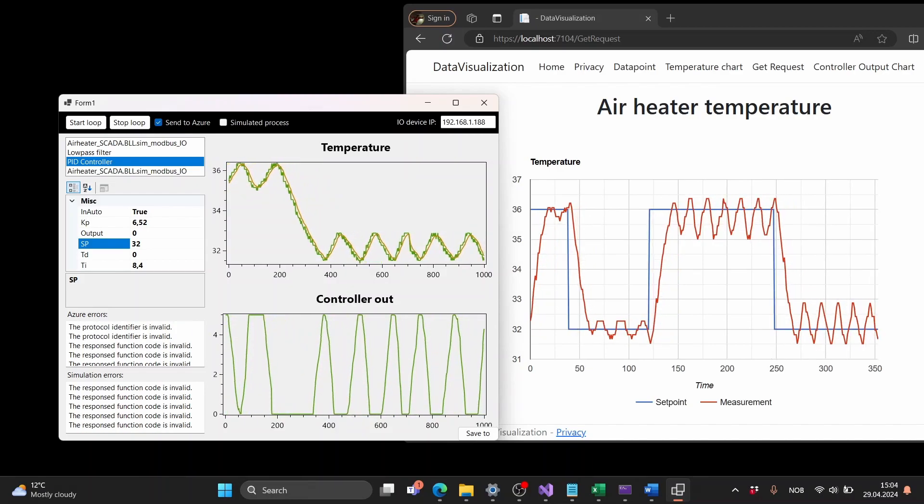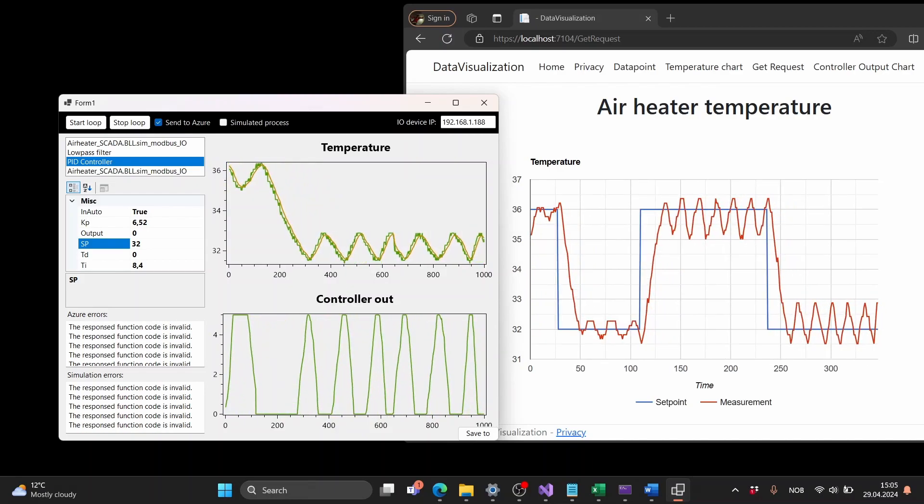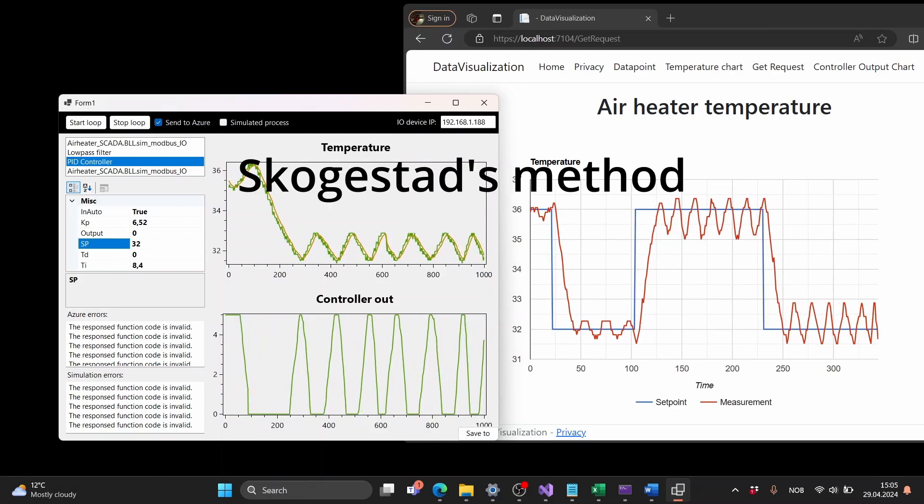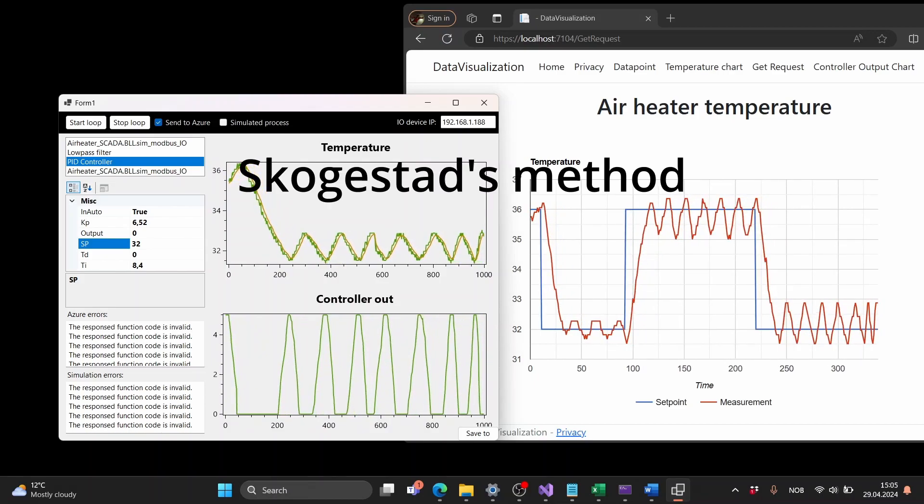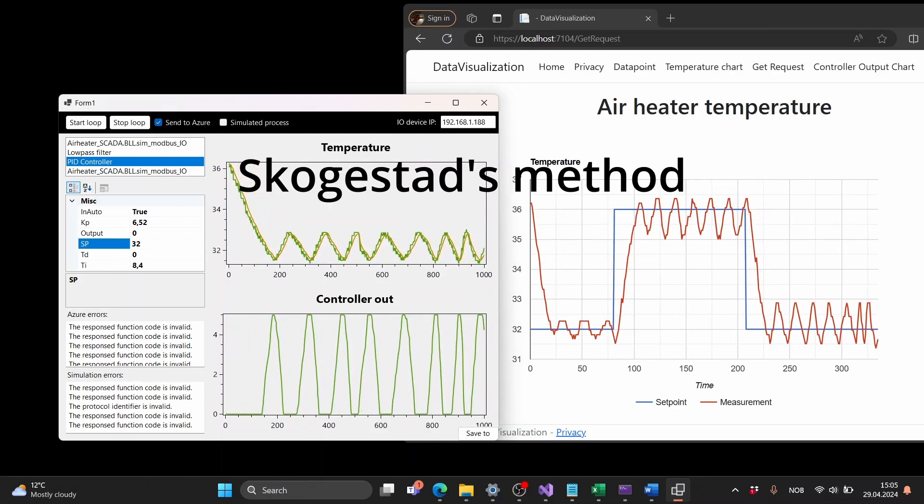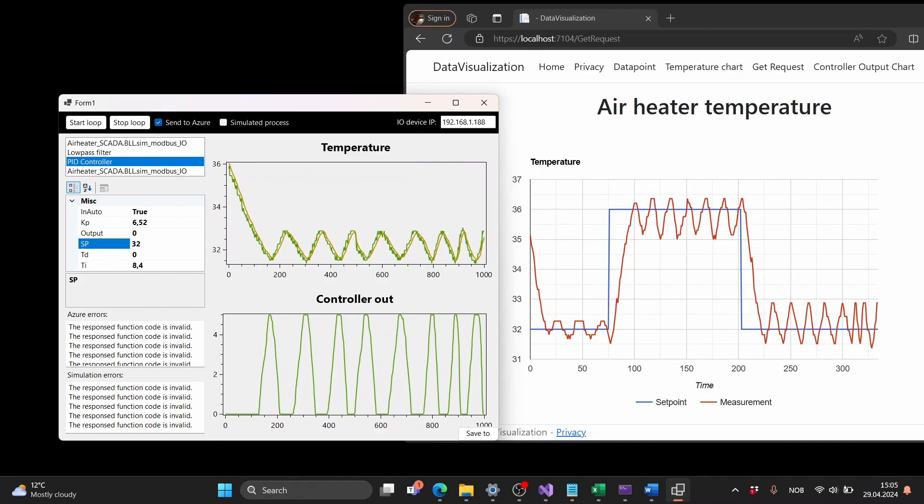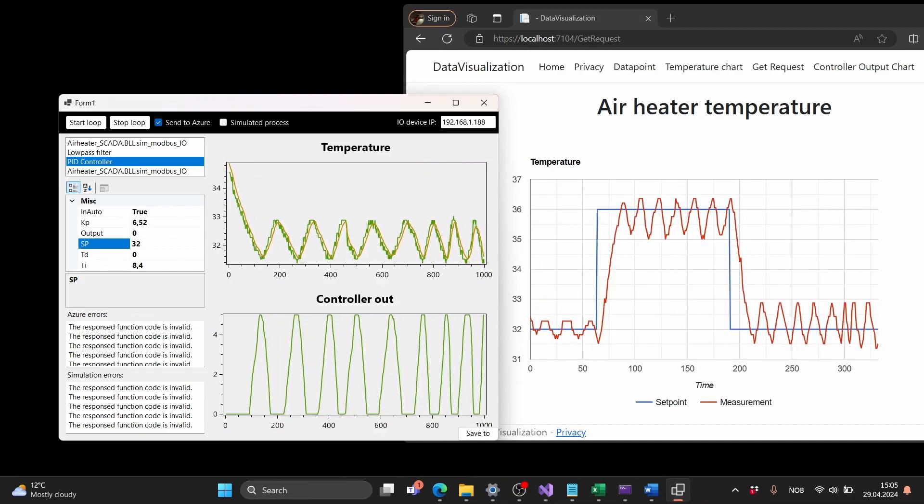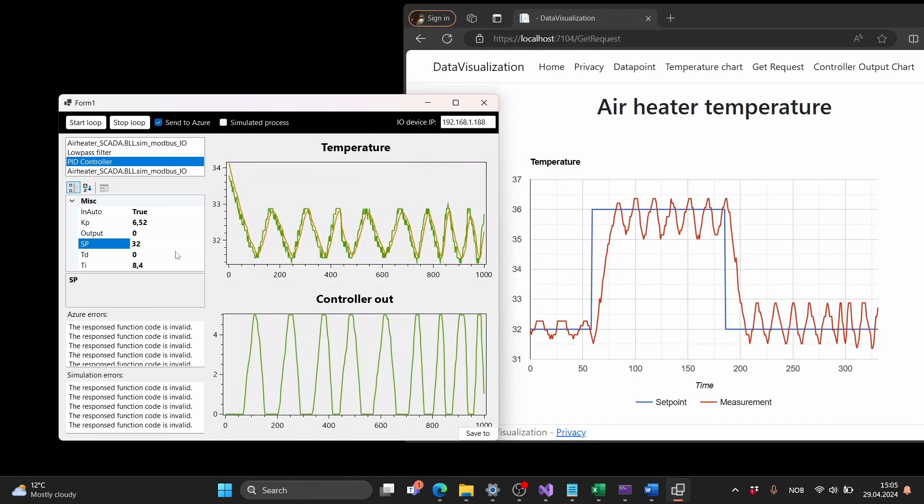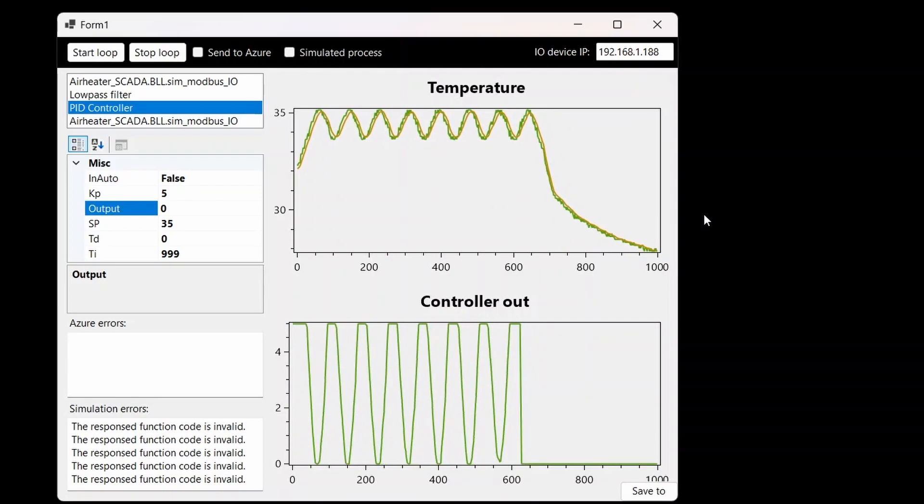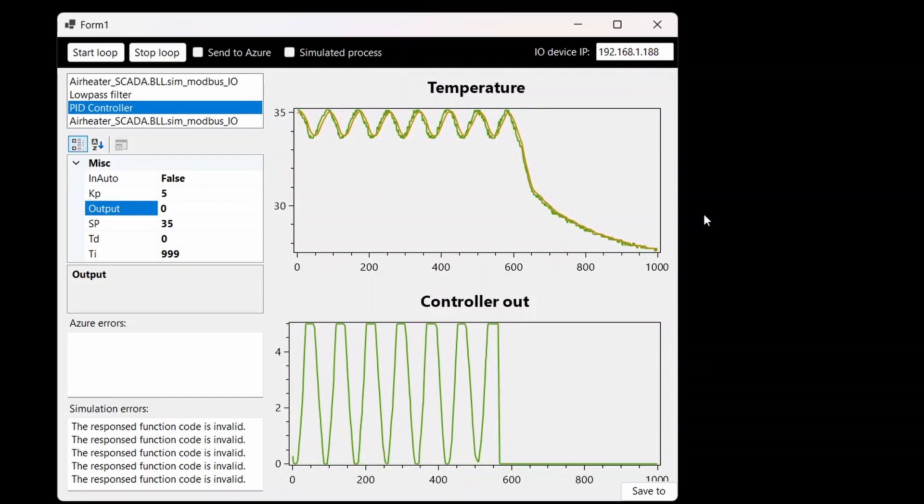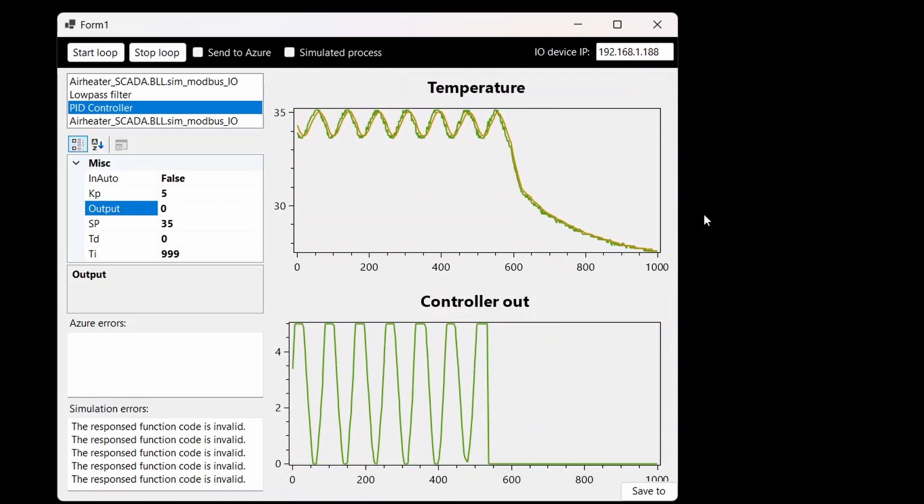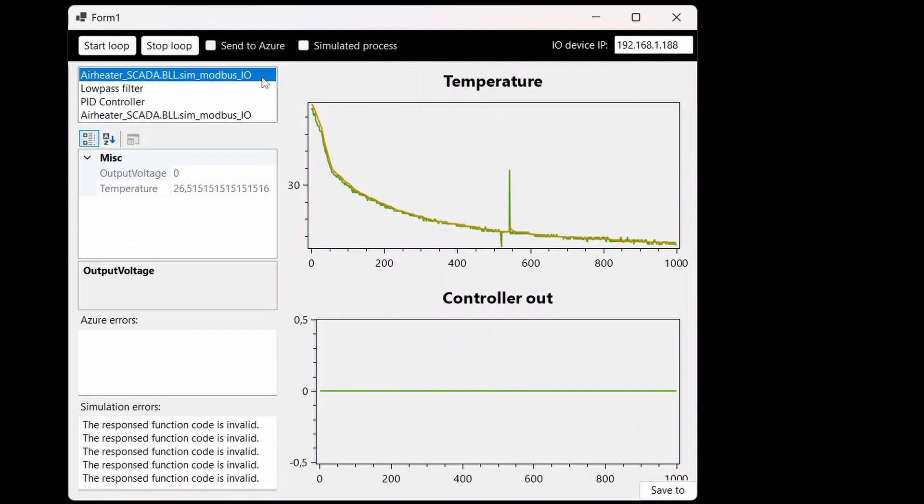We can do this by trial and error but now we are going to use the Skogestad method. This method is an open loop tuning method and we need to set a fixed control signal for the heating element. We then need to wait for the temperature to get stable and we can then do a step change in the heater power and see how the process responds.